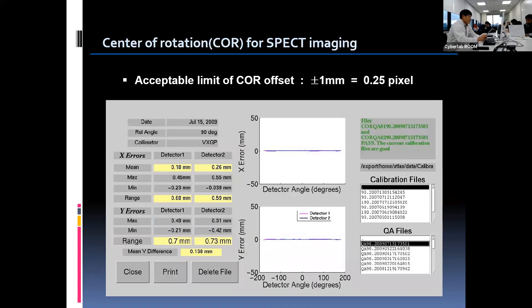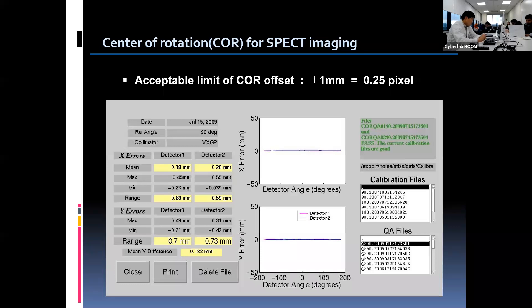When the acquisition is done, the computer calculates the correction factor for variation of the detector position. This is the COR test report that the computer generates. The alignment should be checked in both x- and y-axis. Manufacturers provide software for alignment, calculation, and correction for COR variation so that offsets are easily corrected by the computer. The acceptable COR offset limit is ±1 mm, which corresponds to 0.25 pixel.